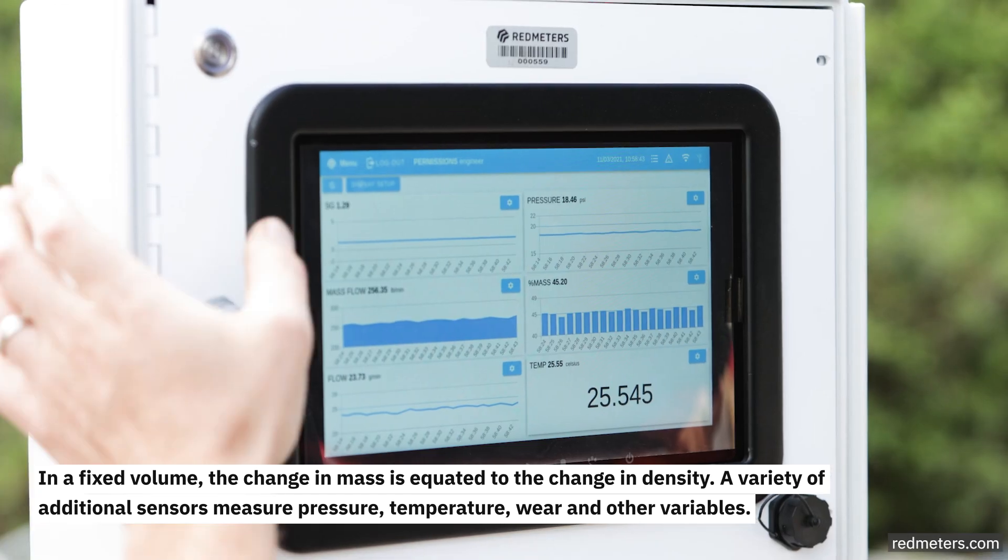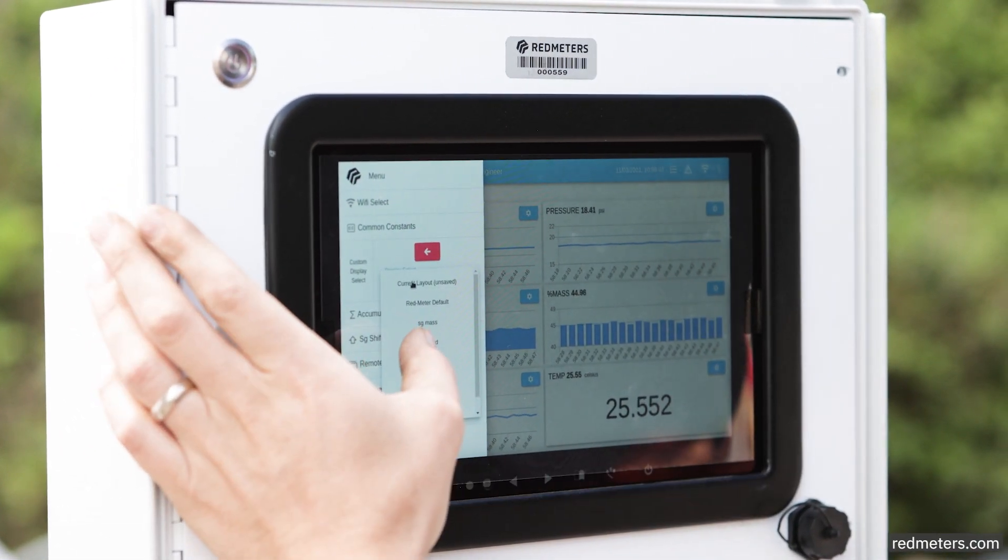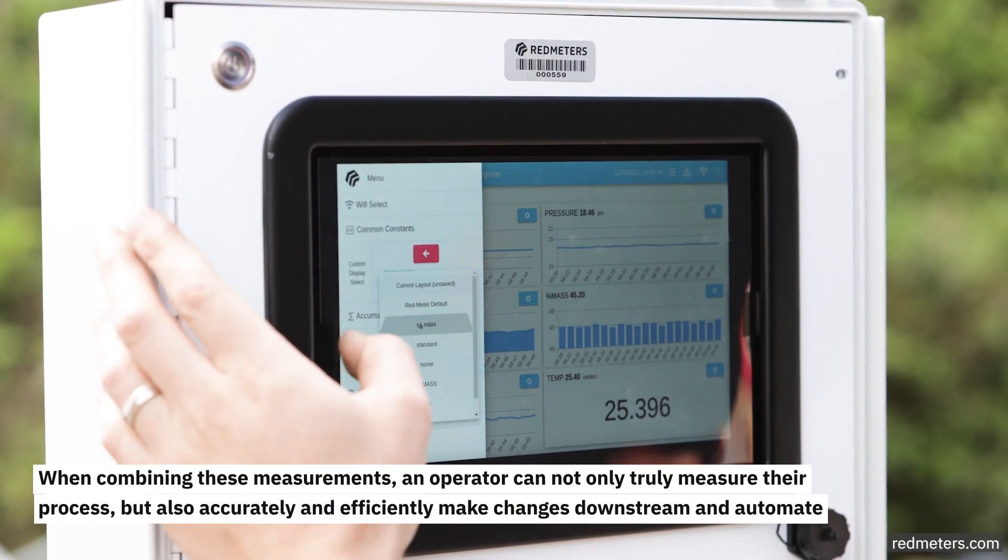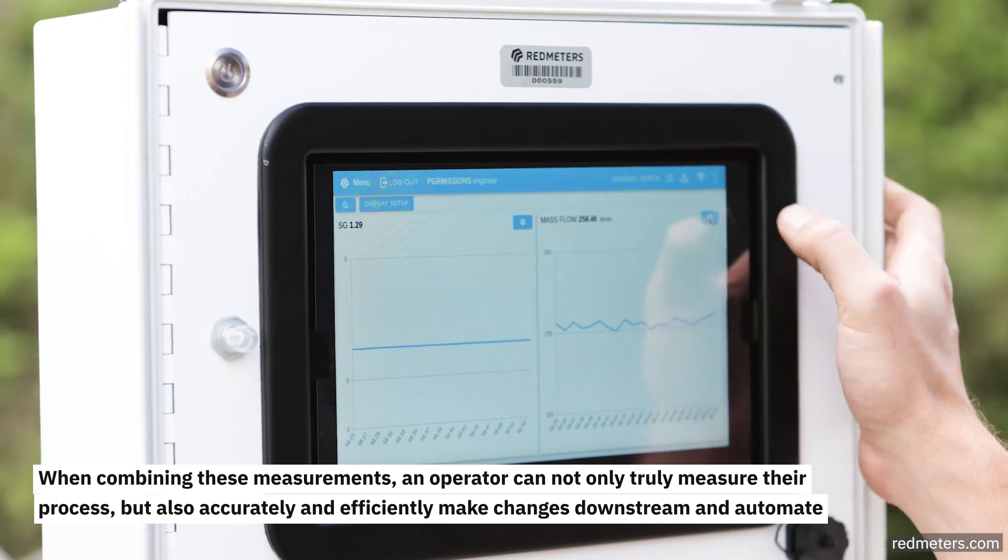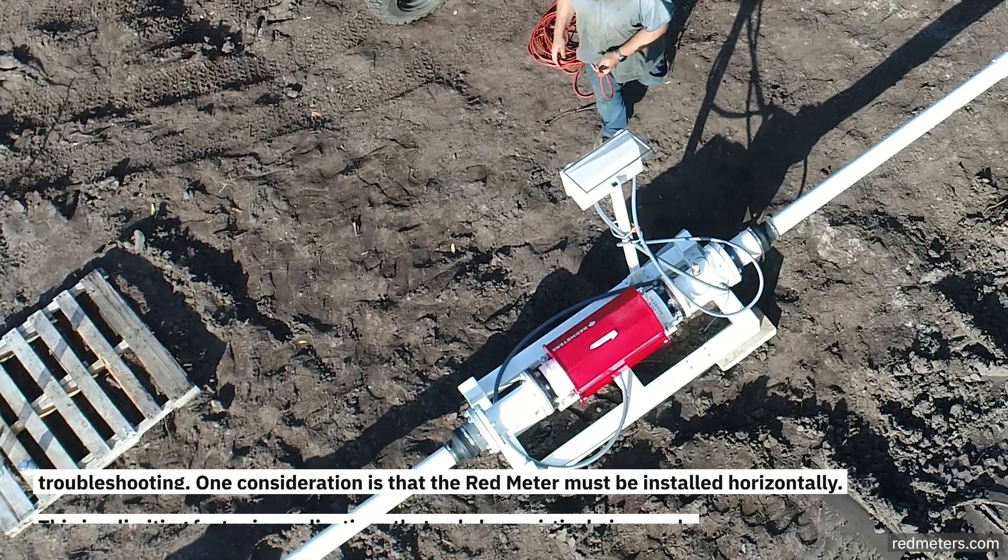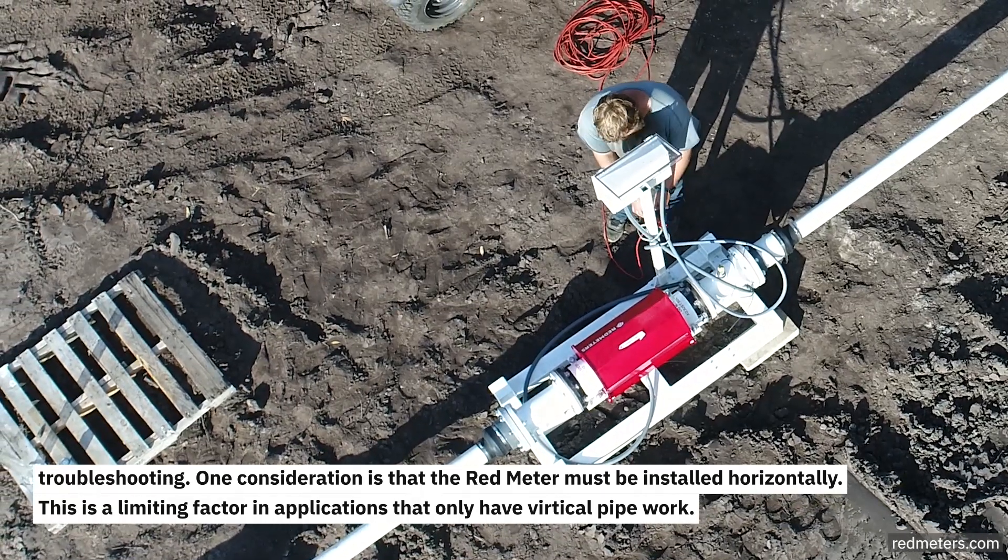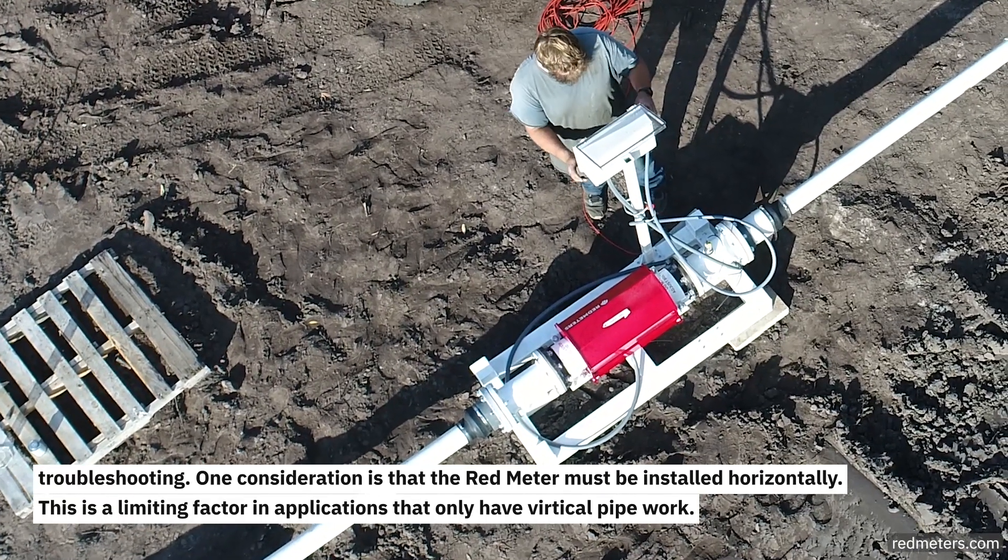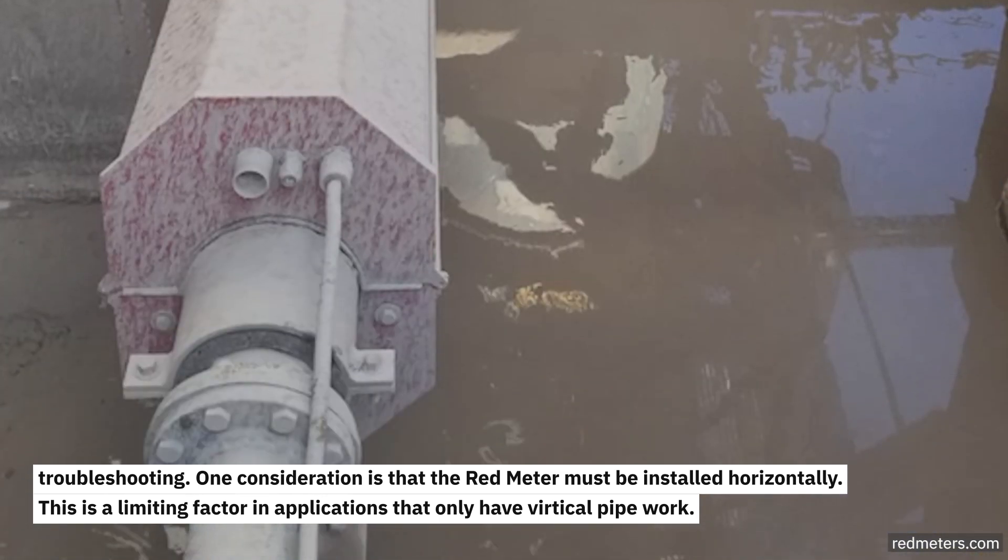A variety of additional sensors measure pressure, temperature, wear, and other variables. When combining these measurements, an operator can not only truly measure their process but also accurately and efficiently make changes downstream and automate troubleshooting. One consideration is that the Red Meter must be installed horizontally. This is a limiting factor in applications that only have vertical pipework.